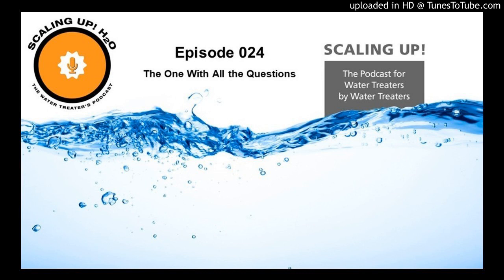Now, it should really be oxidation/reduction potential. Now, oxidation, if I can take you back to chemistry class, is the loss of electrons, and reduction is the gain of electrons. Normally, we will find ORP on a controller where we have a cooling tower where we are feeding oxidizing biocides. And it is simply just telling us how much oxidizing biocide we have in that system, and is it enough for our program to effectively kill the stuff that's growing in the cooling tower.